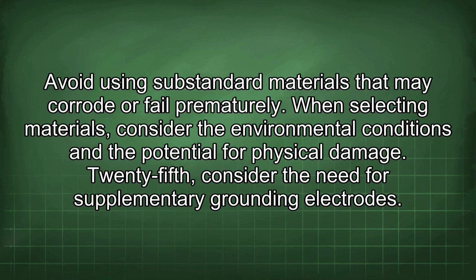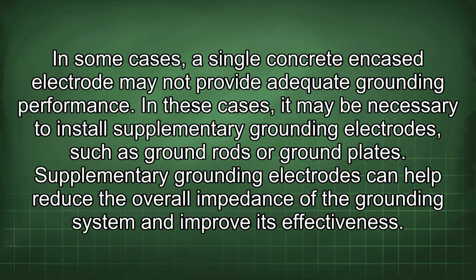25th, consider the need for supplementary grounding electrodes. In some cases, a single concrete encased electrode may not provide adequate grounding performance. In these cases, it may be necessary to install supplementary grounding electrodes such as ground rods or ground plates. Supplementary grounding electrodes can help reduce the overall impedance of the grounding system and improve its effectiveness.